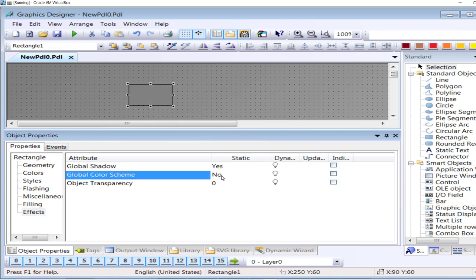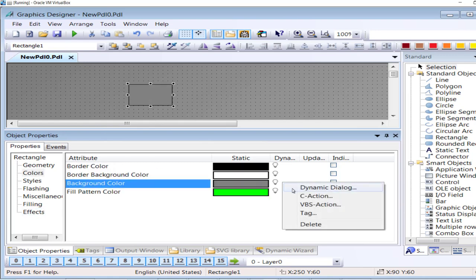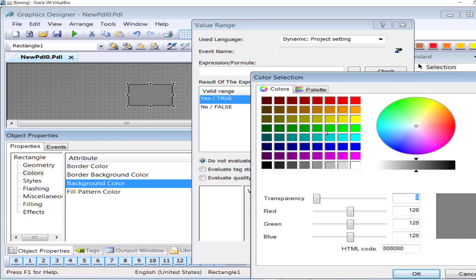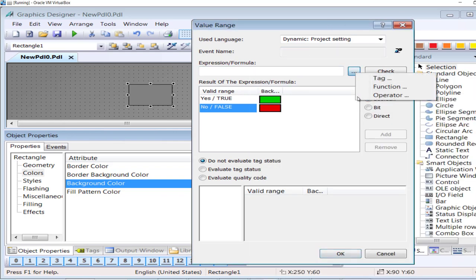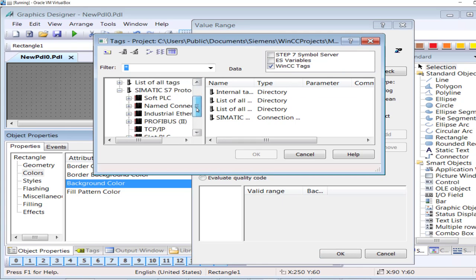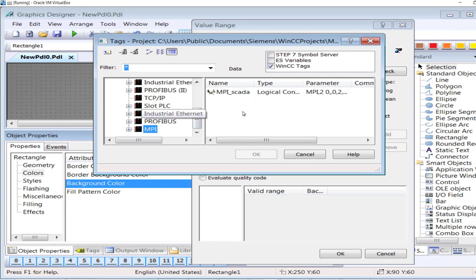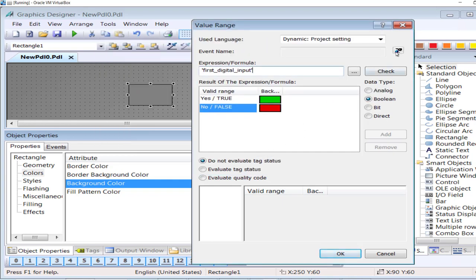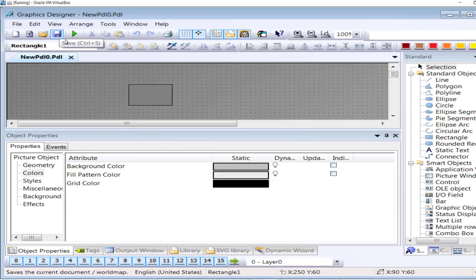For demonstration purposes, I will take a rectangle and go to its properties. I will set the global color scheme so that the background color is associated with the status of the digital tag entered in WinCC Tag Management, using a dynamic dialog. The tag type is boolean — if the digital channel status is high, the color will be green; if it is low, it will be red. The tag is the MPI SCADA connection, first digital input I 0.0. I will save the project.